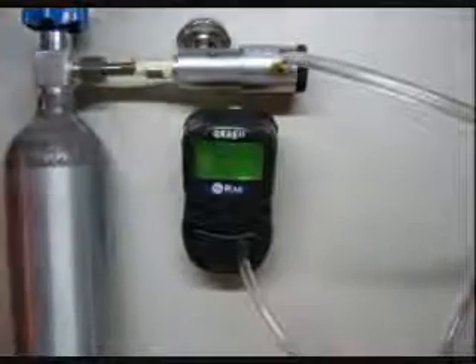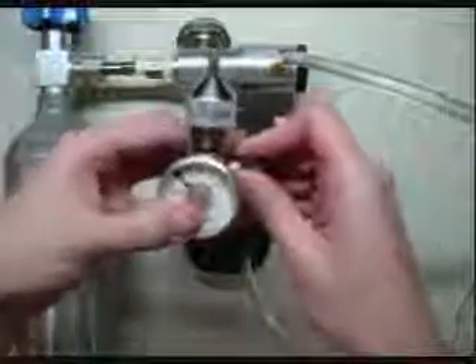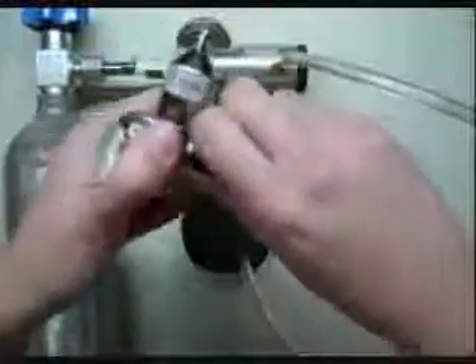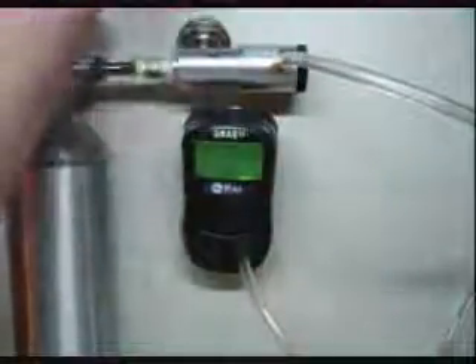If you are calibrating with a normal disposable cylinder with a regulator shaped something like this, what you'll want to do is before you screw it into the top of the cylinder here, you'll want to open it up, screw it into the cylinder, and then once you can hear the gas flowing, you can go ahead and close it again. Again, that's just to make sure that the gas doesn't mix with the outside air inside that regulator there.